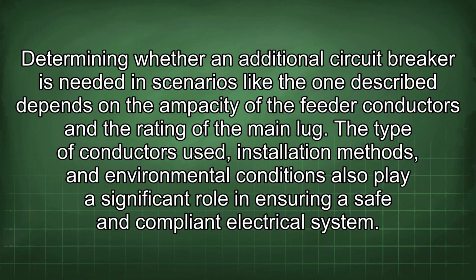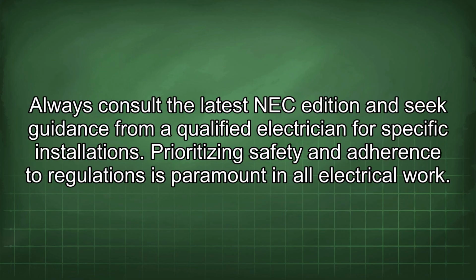Determining whether an additional circuit breaker is needed in scenarios like the one described depends on the ampacity of the feeder conductors and the rating of the main lug. The type of conductors used, installation methods, and environmental conditions also play a significant role in ensuring a safe and compliant electrical system. Always consult the latest NEC edition and seek guidance from a qualified electrician for specific installations. Prioritizing safety and adherence to regulations is paramount in all electrical work.